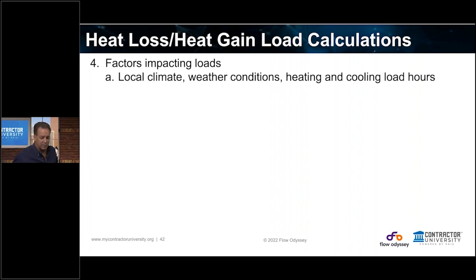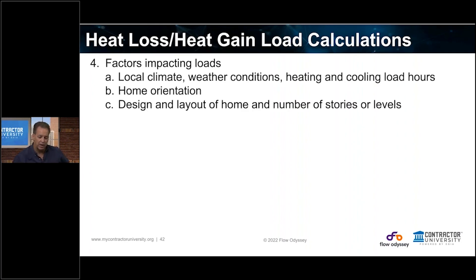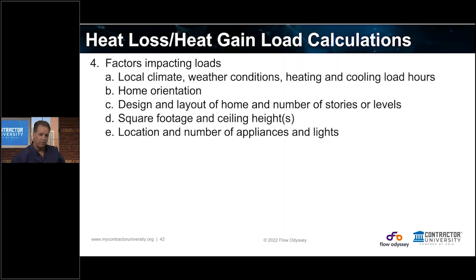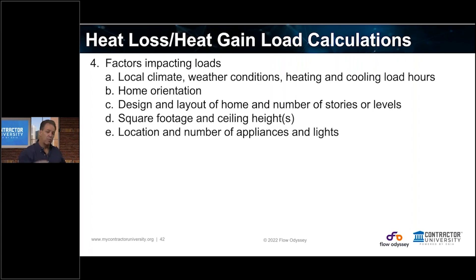What are some of the factors impacting the loads? It's local climate, weather conditions, and heating and cooling hours. It's the direction the home faces, the design and layout, number of stories, square footage, ceiling heights, location, number of appliances, and lights. We don't factor lights in except for about two watts per square foot on a residential load — but if they have a lot of can lights or halogen lights, it's huge, they throw off a lot of heat. In a commercial load calculation, you actually have to factor in each ballast.